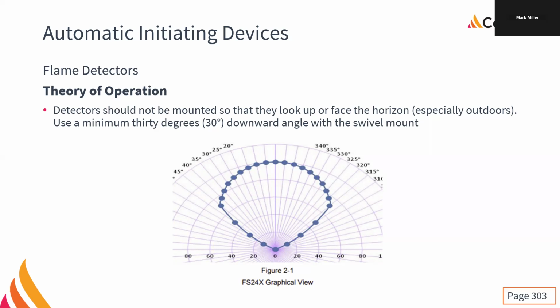Because they're line of sight, it's very important that we mount them correctly. We do not want them looking up. We do not want them facing the horizon if they're outdoors. Typically, we want at least 30 degrees down. The ones I installed in the aircraft hangar, we put them right up at the ceiling and we actually angled them down at about 45 degrees because we had to be able to catch directly below and then all the way out. If we left them pointing up any higher, then there would have been a very large dead spot near the wall, and everything gets stored near the wall in an aircraft hangar because that's where the planes don't go. So, got to be careful.